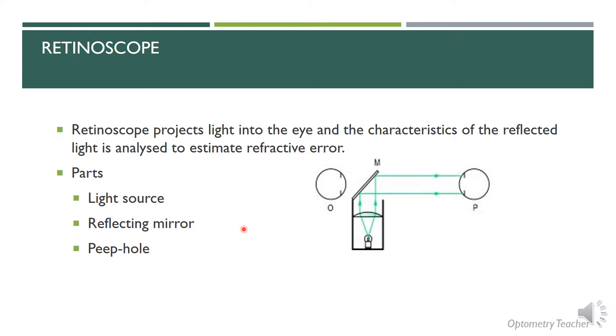Now getting into the retinoscope — it's one of the simplest instruments in eye care. It basically aims to produce a light that is sent into the patient's eye. Whatever light goes into the patient's eye gets reflected from the patient's retina and comes back to reach our eye, so we are able to see a reflective patch of the retina that we call the retinoscopic reflex. For that we basically need a light source, a reflecting mirror, and a peephole.